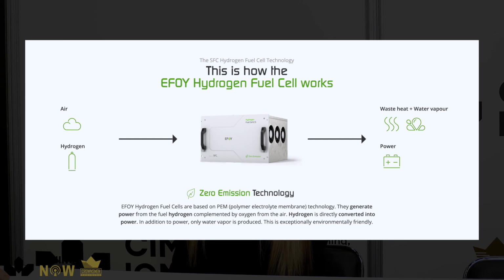What we're typically doing when we're looking at the methanol fuel cell specifically, we're incorporating renewables. So you'll have your solar array, you'll have your battery bank. Sometimes you can use wind as well. And then what the fuel cell does is it's monitoring the state of charge on the battery bank that you'd have in that system. So we're allowing you to lead with a renewable energy source, but we're giving you the reliability with the fuel cell on the back end acting as supplemental power. So it starts and stops based on battery voltage when solar can't keep up. Oh, that's very, very cool.